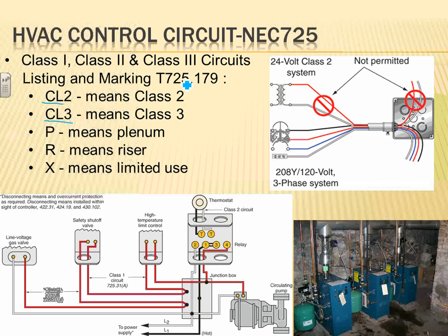And here's my control circuit. Like we said, they cannot enter the same box. I don't know if you can see here. You can't put them in the same box or the same conduits because they're insulated differently. And here's my class 2 circuit thermostat for this circulating pump.